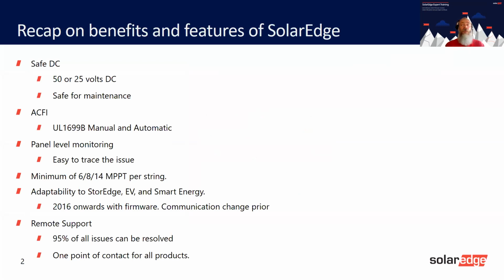So I just want to start, for the ones that are new to SolarEdge and for the ones that have been installing, with a recap of some of the safety features and benefits of SolarEdge. The first one is Safe DC. We're the only manufacturer that has this Safe DC. For commercial, it will reduce your string voltage down to below 50 volts. For residential, below 25 volts.